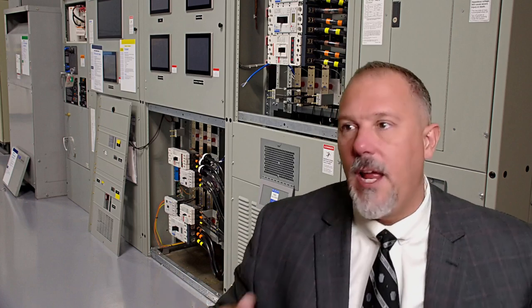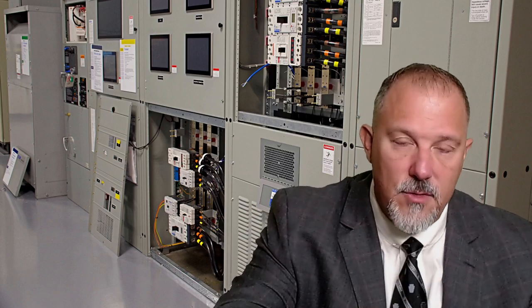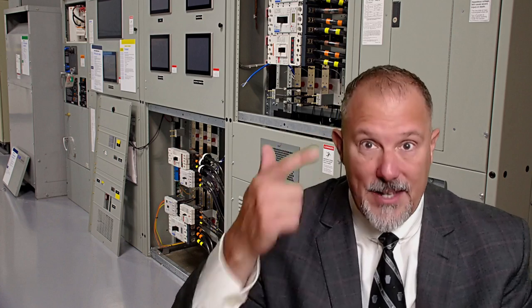As long as your available fault current is greater than the rating, you can't predict whether or not you're going to have a bolted fault, an arcing fault, or a ground fault. Remember, just like in selective coordination and other topics, you have to compare how much current will pass through this equipment with its rating. Properly applied equipment helps increase electrical safety. If it's misapplied, your hazard awareness alarms need to go off.